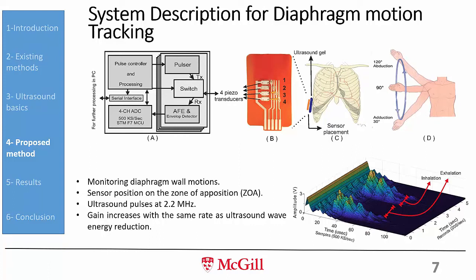At the bottom here, you can see this is the 5-second data that we get from one transducer. And basically, you see that when the person has an inhalation, we get a reflection back from the diaphragm, whereas when the person has an exhalation, there is no reflection, so all the signal passes through. So it's very easy to detect inhalation and exhalation from the received signal.